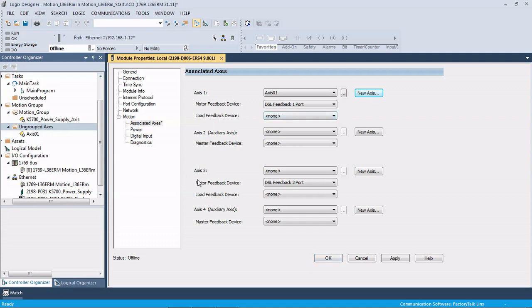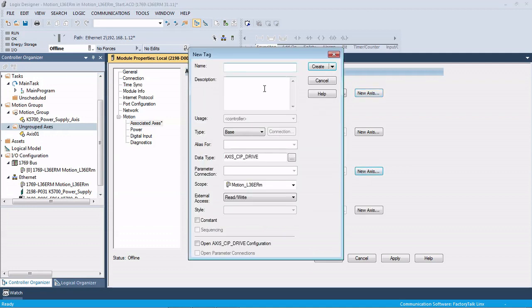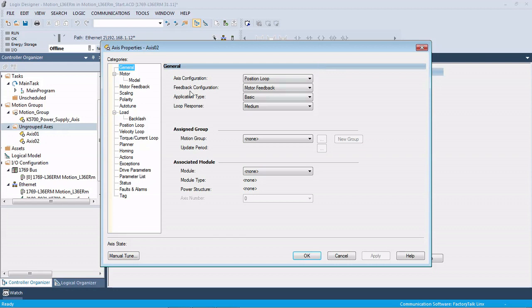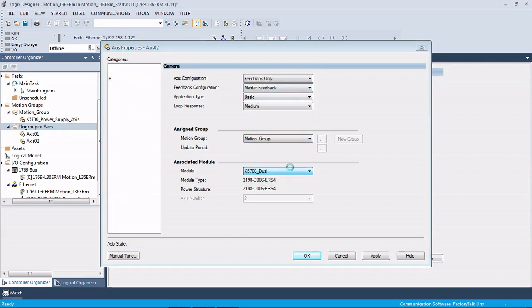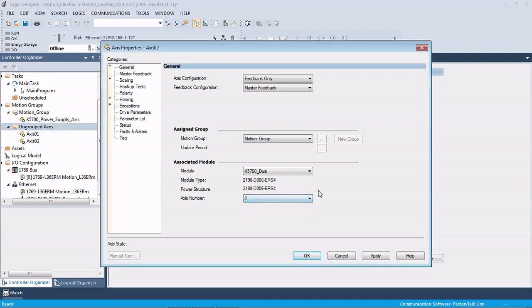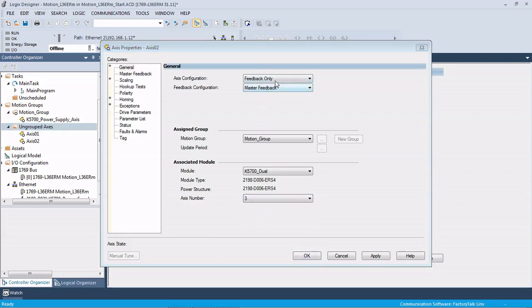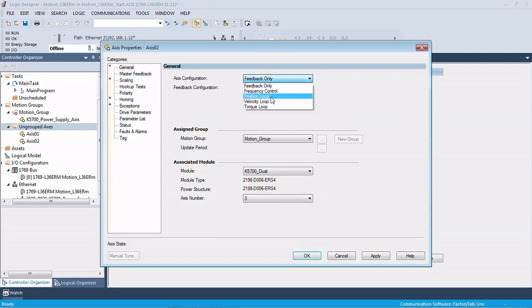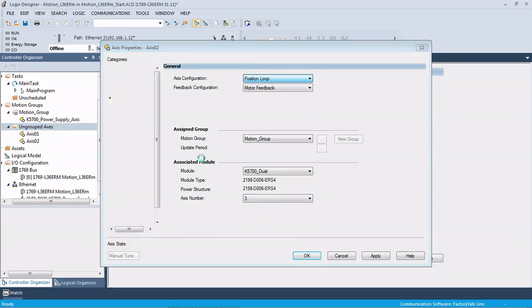Then it brings us back here and our axis 3, that would be our second physical axis. So we're going to create one there. Position loop again, motion group, tie it to our drive. You can see how it changed it to axis number 2, but axis number 2 is feedback only, so we want to change that to axis 3 and make this a position loop.